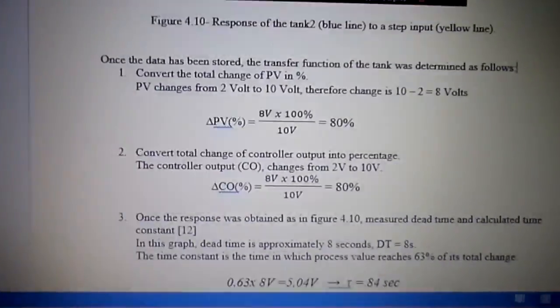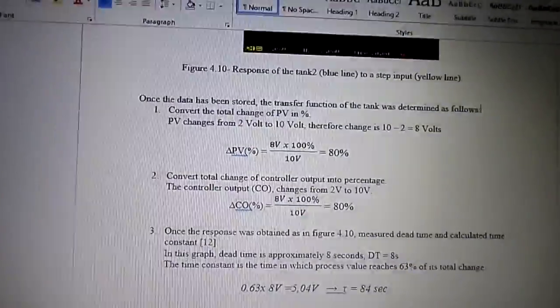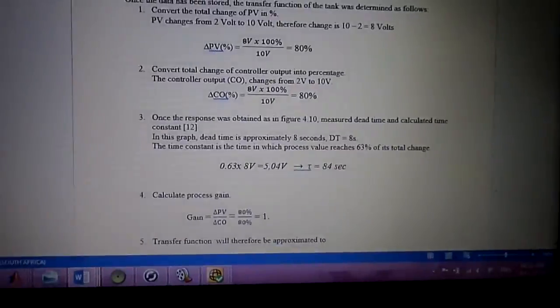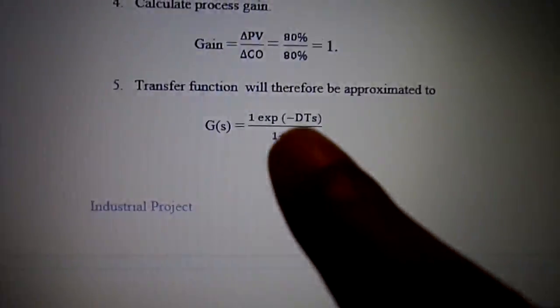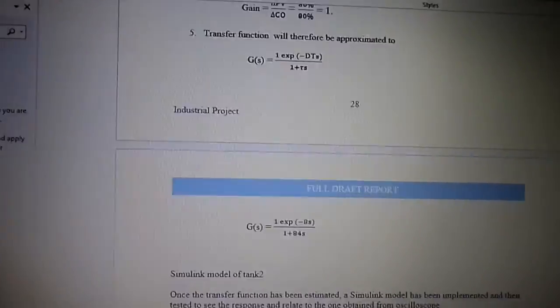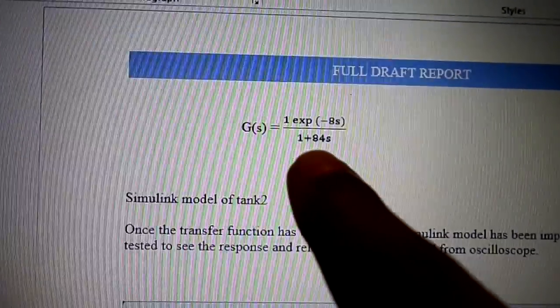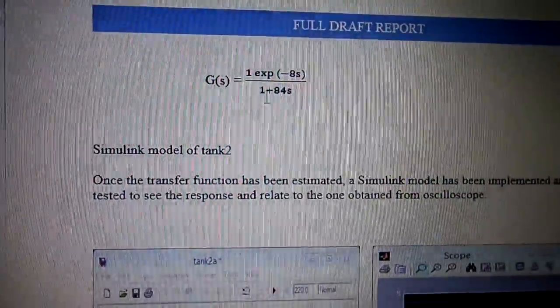Which is what I'm going to show you just now. From that plot I measured that my time constant is 84 seconds and my dead time is 8 seconds, so this gives me my transfer function. I have this document which, if you're interested, I can gladly supply to you — that's the formula.